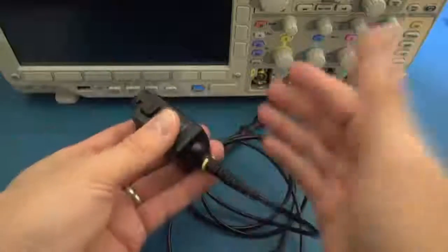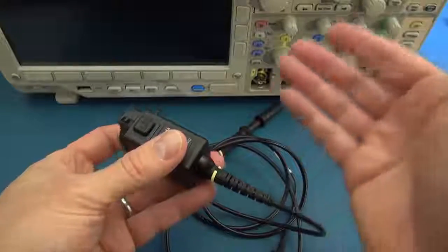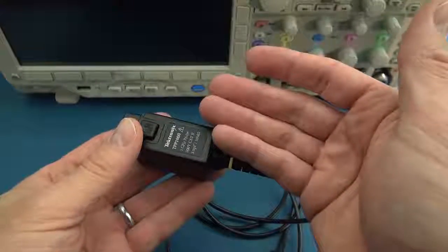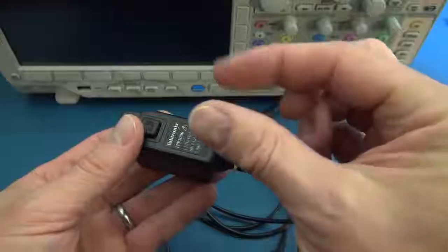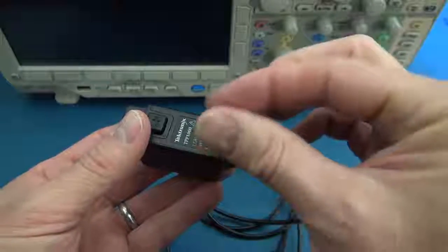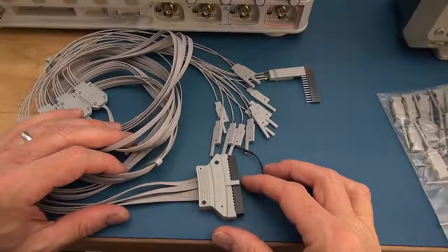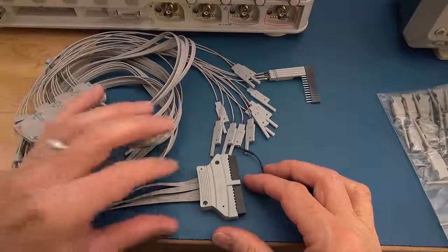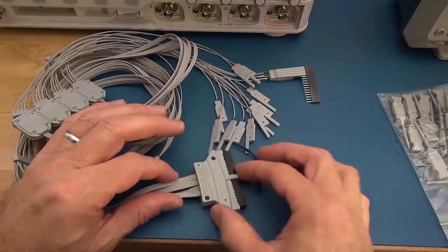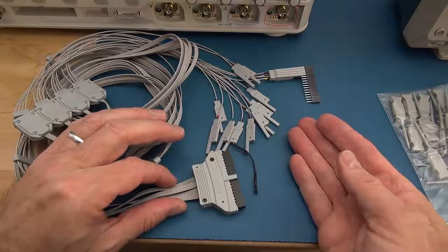The Tektronix does not have a compensation screwdriver, as that's all done within the scope. The Keysight does part of that in the scope, but if the setting is too far out, it'll ask you to make adjustments with the adjustment screwdriver. If you purchase the mixed signal option on any of these scopes, you'll then get a set of digital probes to look at logic signals.